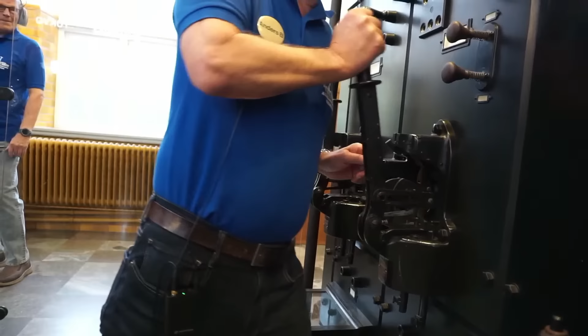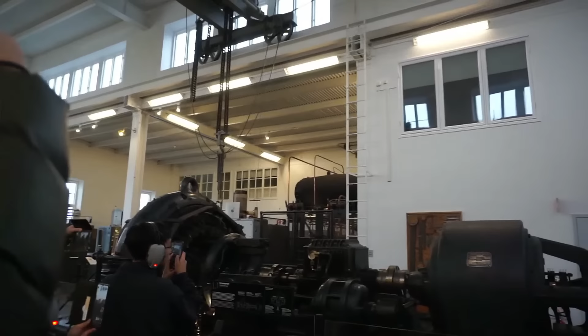I will connect a zero voltage release and the main motor with an oil switch. There's oil in the switch to extinguish electrical arcs. Now the alternator starts to rotate. There are large masses to be handled. Only the disc weighs about 1,500 kilograms. On the ammeter here we can follow the start-up current, about 145 amps.